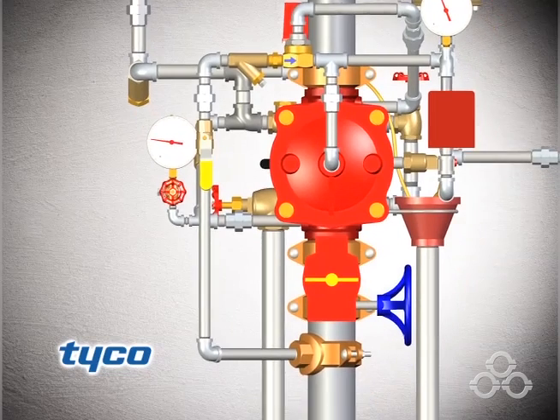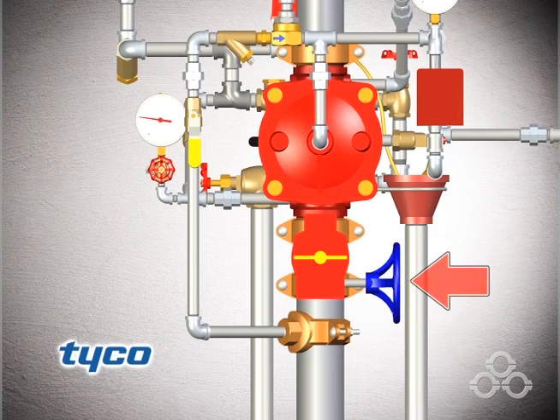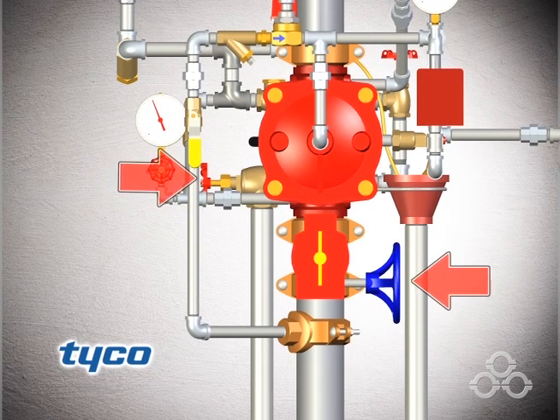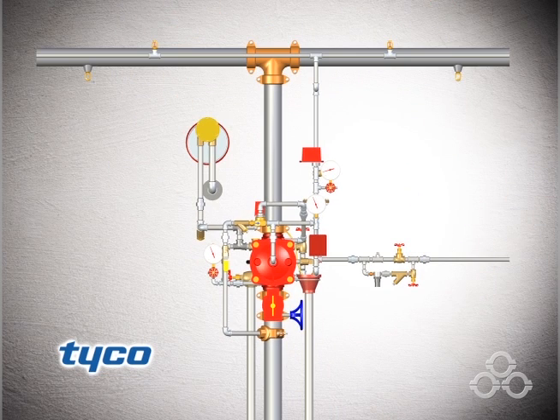Finally, slowly open the main supply control valve and close the main drain valve once water begins to discharge from the drain. The system is now ready to return to service. Thank you.